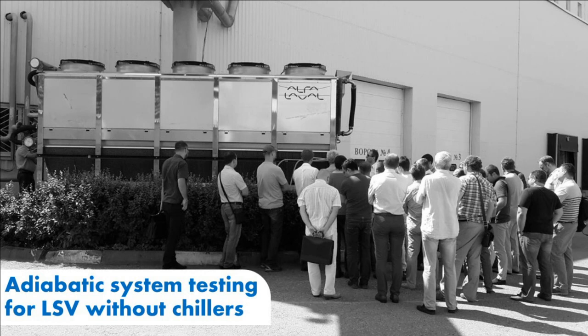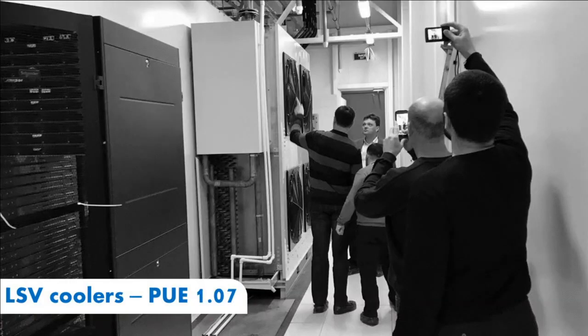DataPro also tested the low-speed ventilation system with adiabatic coolers without chillers. In the summer, many colleagues from the data center industry were invited to test in order to personally verify the effectiveness of the system. The power consumption of a 125 kW low-speed ventilation unit is 1 kW, with an estimated PUE of 1.07.